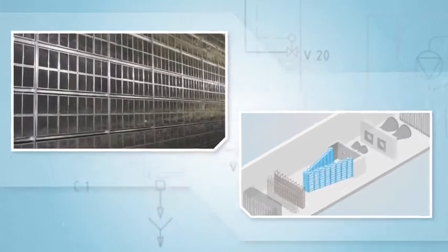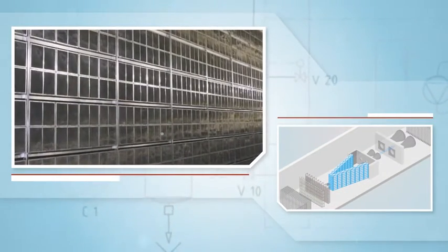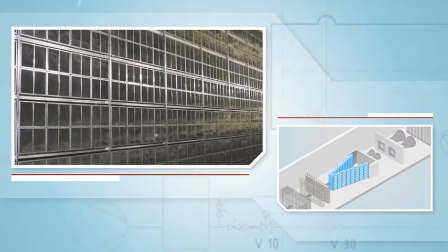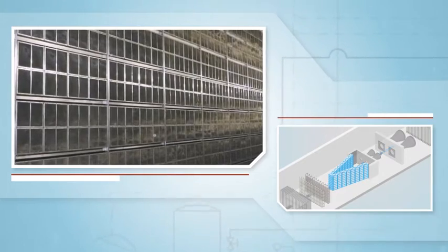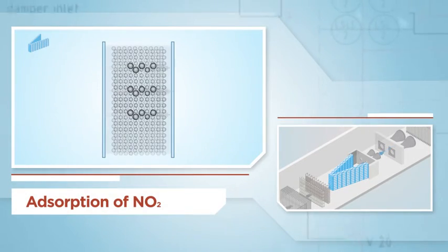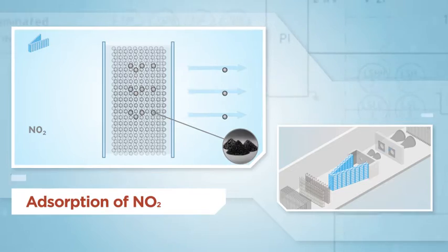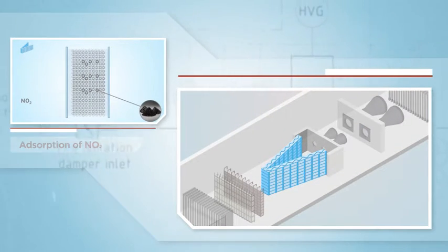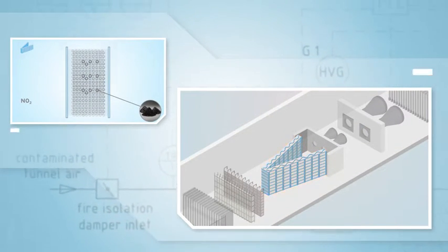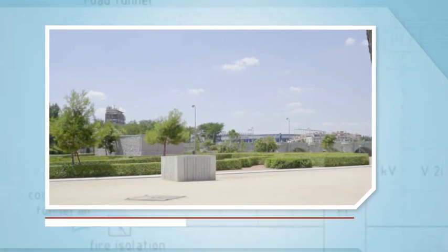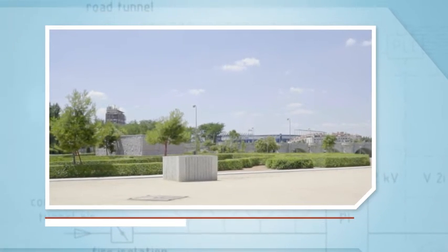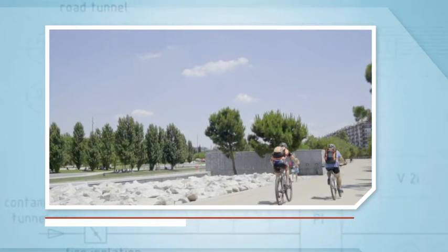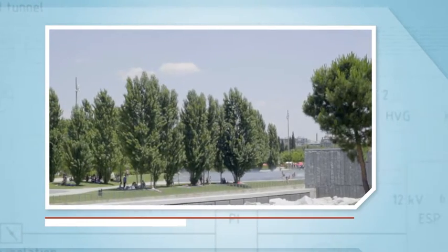After the electrostatic precipitator, the air passes through the active carbon filter to capture the noxious nitrogen dioxide gases by adsorption. As a result, the air released into the atmosphere contains fewer gaseous and pollutant particles than the air usually found in the environment around the tunnel entrances.